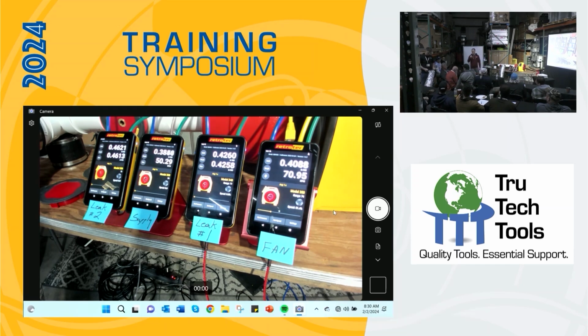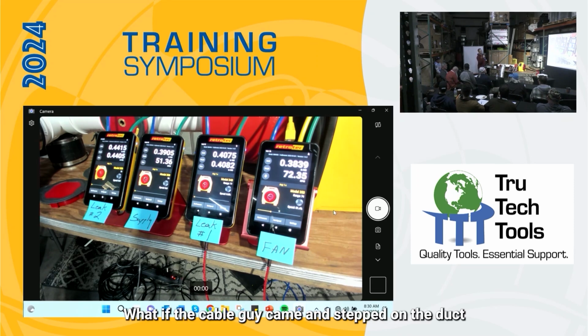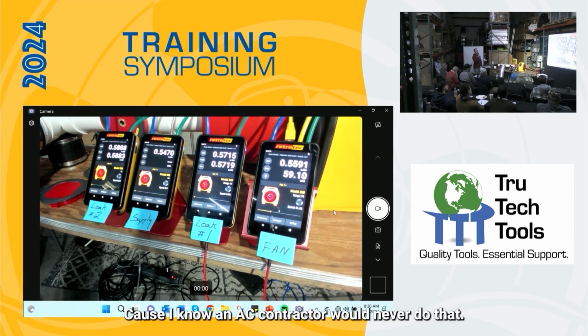Yeah, so it's kind of like having a piece of sheetrock over your supply boot and not cutting it out. We were at 50, so the starting 51 was at 51. Yeah, not a whole lot changed there. Exactly. So we're losing some flow there.